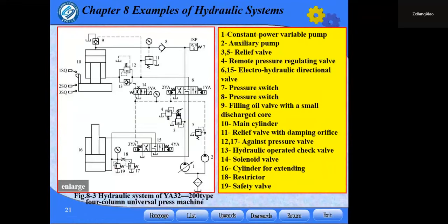Note that because of high pressure oil in the bigger diameter cylinder with large stroke, the liquid saved a great amount of energy due to the oil compressed in the pressure holding process. If the upper port is connected to the return oil line, the energy saved in the oil will release suddenly, resulting in hydraulic impulsion, vibrations to the machine and the pipeline, and thus noise. It is necessary to emphasize that pressure releasing is necessary when pressure holding is ended and the cylinder will be retracted.